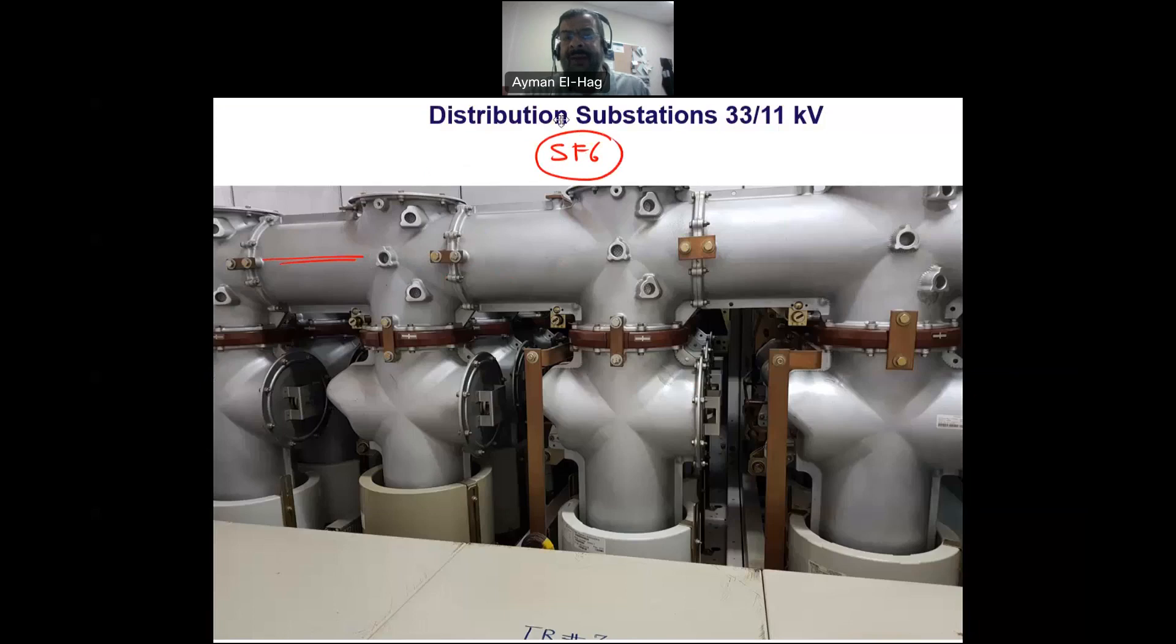SF6 is well known as a very good insulating gas that we use in high voltage applications. You see these bus bars are all for grounding. The whole structure outside is grounded, so even if the substation is energized, you can safely touch the substation because everything has zero potential.